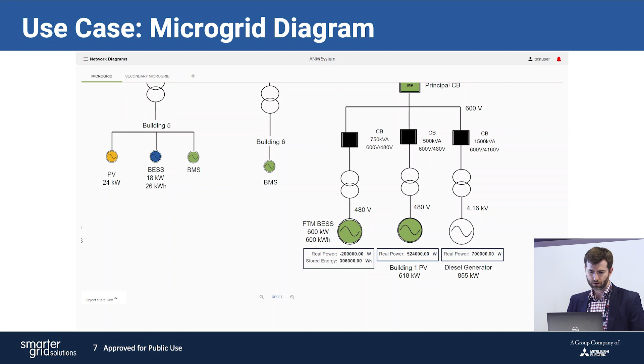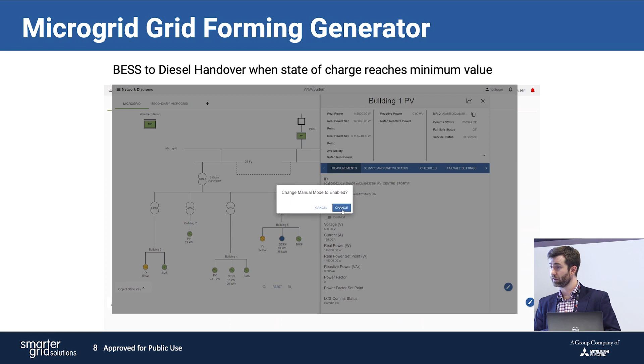Another example here - not everything, but a lot of control actions when controlling a microgrid have to be automated for fast response and stability, but some things can be manual. You can see here I'm throwing this battery, it's a PV system, into manual mode so we can give it hard set points. It's really important to give the operators of the microgrid control over their assets. They need to know they can pull the plug or run maintenance, turn things on and off at will, and that the microgrid will stay up.